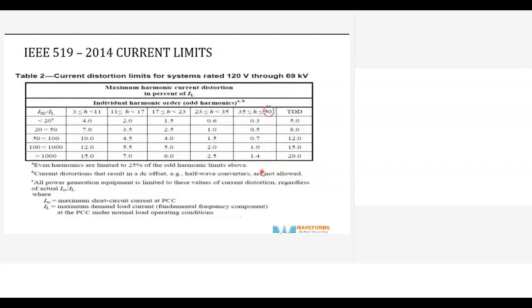This is the current limit for individual harmonics. What you can have depends on the short circuit rating of your transformer. The short circuit ratio is ISC divided by IL. If it is less than 20, you can have a total demand distortion of 5%. But if it is very high, say more than 1,000, you can have a distortion of 20%. So with higher ISC/IL, you are permitted higher distortion. This is available everywhere, so I need not spend more time on this. I will go through this.